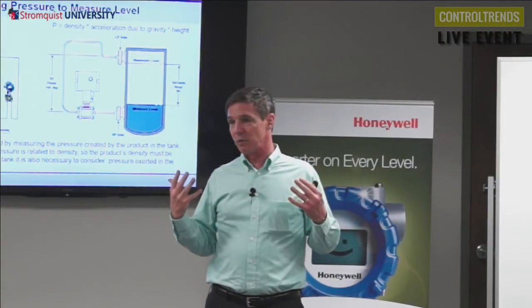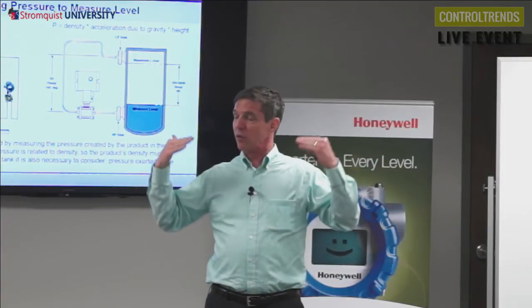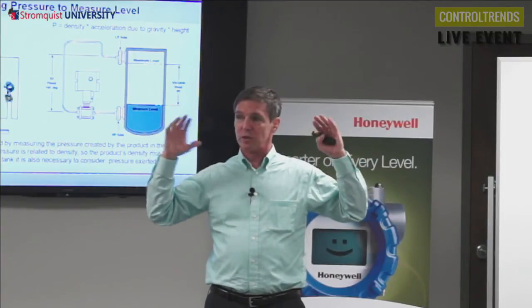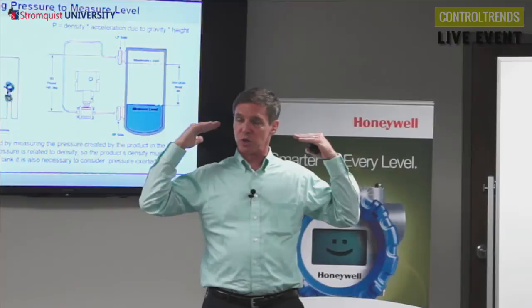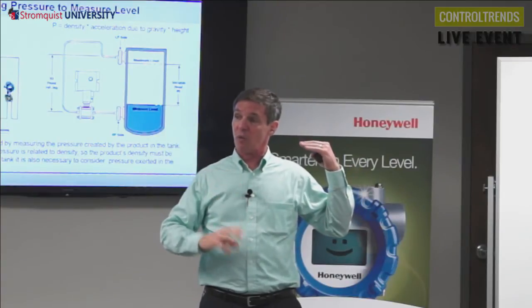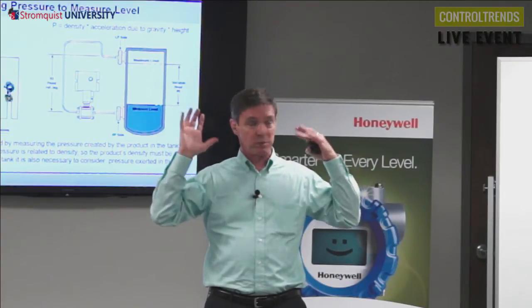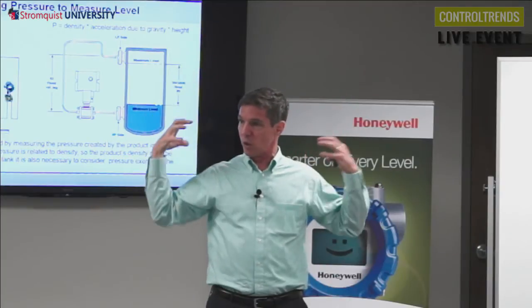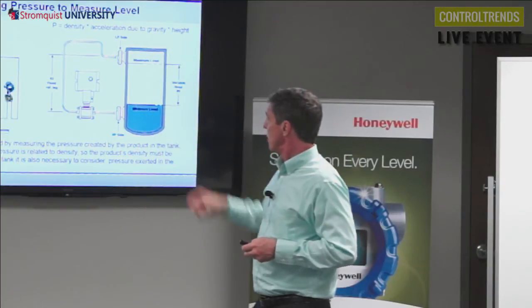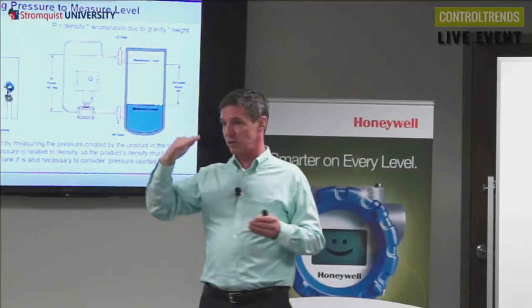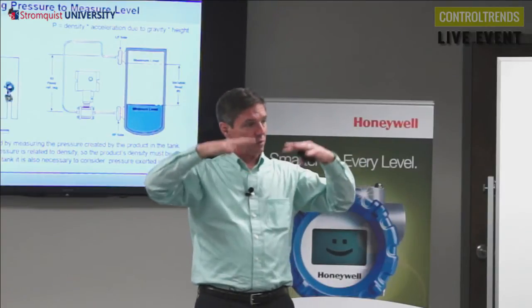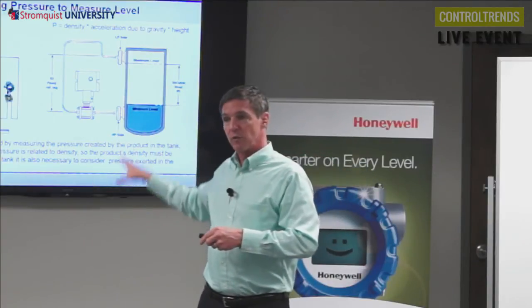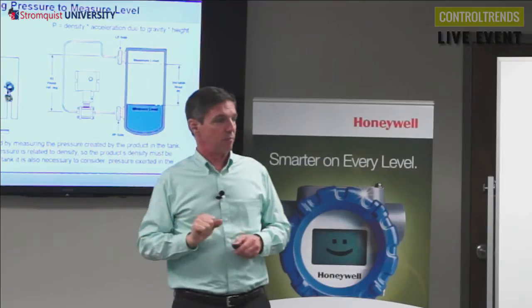We all understand that when you're in a swimming pool, just at the surface, you don't feel much pressure in your ears, but the deeper you go, the more pressure you feel on your ears, because there's more liquid above you that's creating that pressure. That's what's happening here: as the level increases, there's more pressure being exerted by the weight of that fluid, and the differential pressure transmitter measures that.